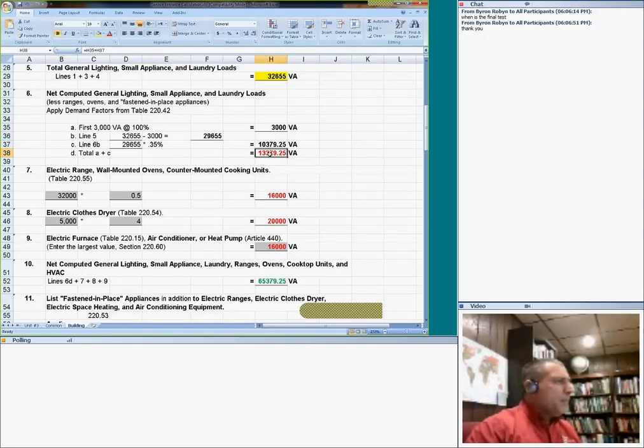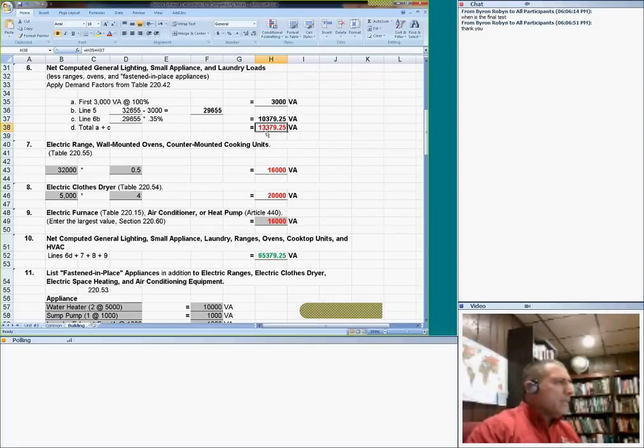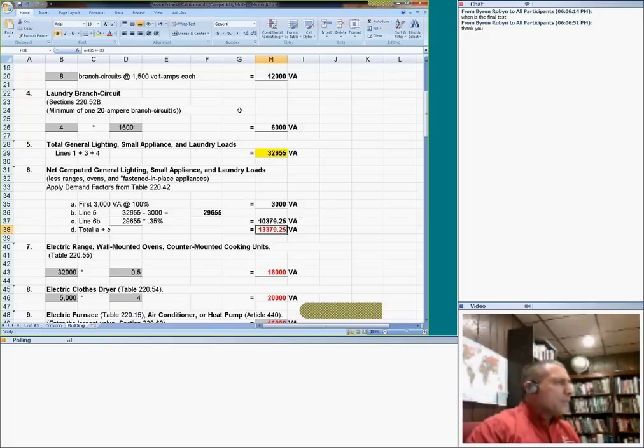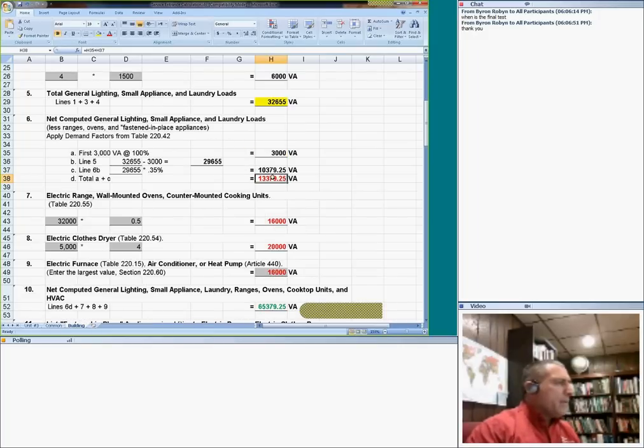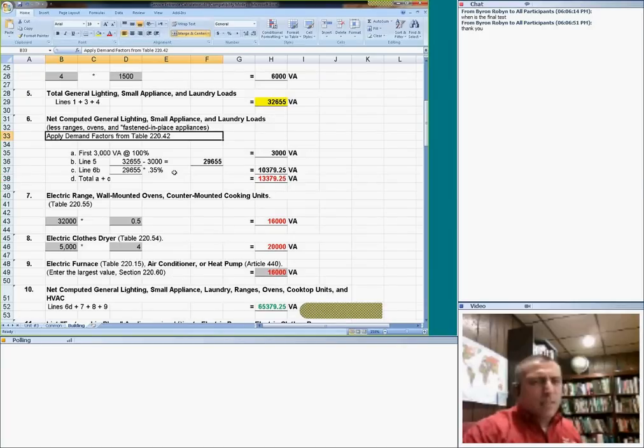Then you add these two, and that will be the demand for this step. That will give the demand for this step. So first add them up, then you apply the demand factor for them, and this demand from table 220.42.